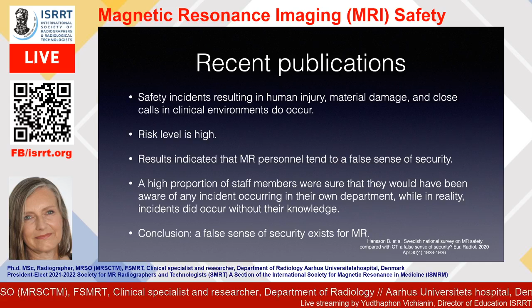And also researchers from the FDA culled data from 2008 to 2017, and it showed that the majority of these events have known causes and therefore they are preventable, and they had more than 1,500 adverse event reports. The reports are from MRI, PET MRI and nuclear MR spectroscopy systems, coils and other components and accessories. As you can see in this table, the majority of the incidents, namely 59%, were thermal incidents, and 9% were projectile and 6% were acoustic.